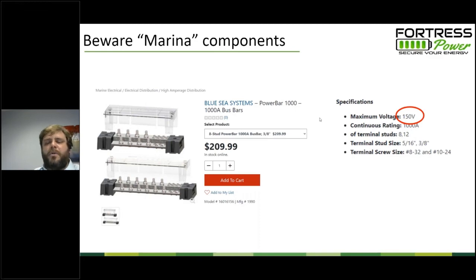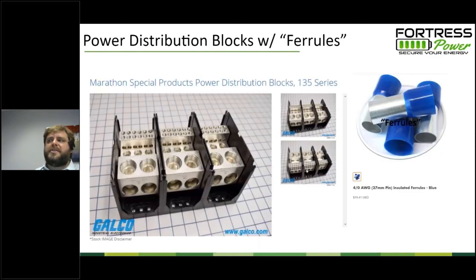A lot of the smaller marina type stuff, the components may only be rated at 12 volts, and you're running it at a 48 volt application. And so they're doing that bus bar rating based off power at 12 volts, not power at 48 volts. And you might find that those cheaper components that are only listed for 12 volt or 24 volt application do not have the same amperage rating when you're running them at 48 volts. And so I would just caution you against getting too cheap, looking for listed parts that are used in other applications, because you might find that that application is a 12 volt application, not a 48 volt application. So it's harder to avoid buying the specialty stuff.